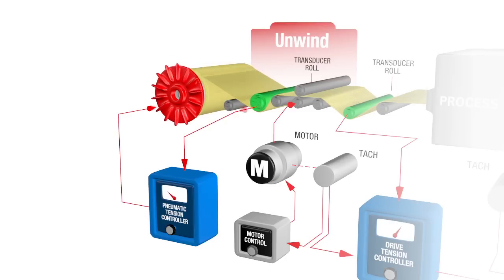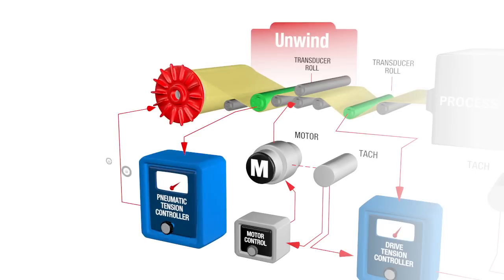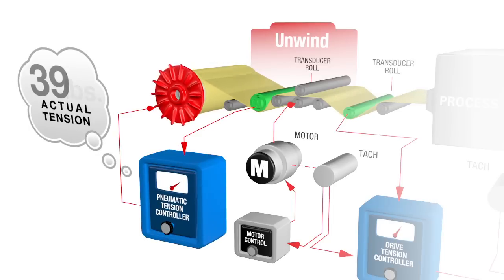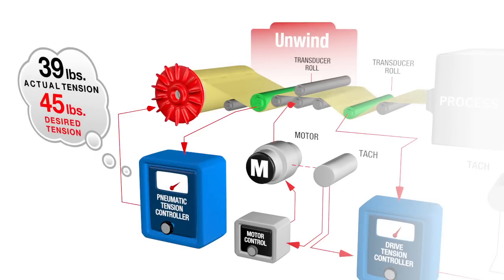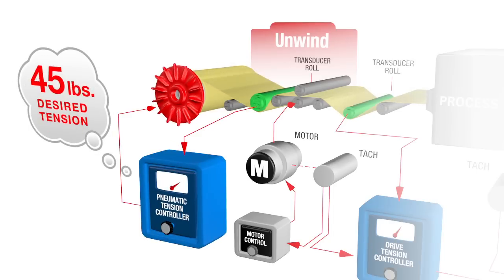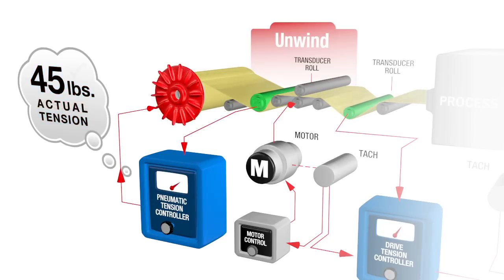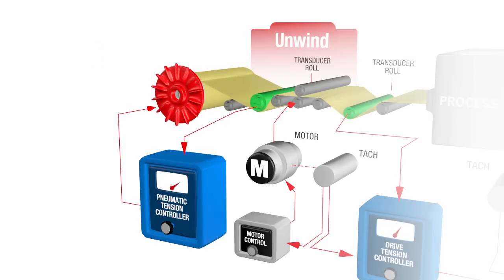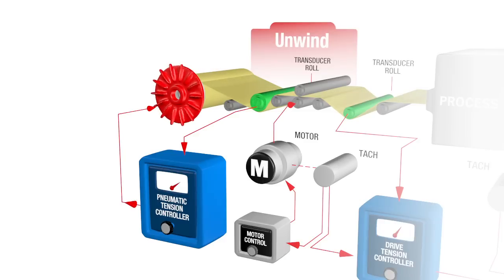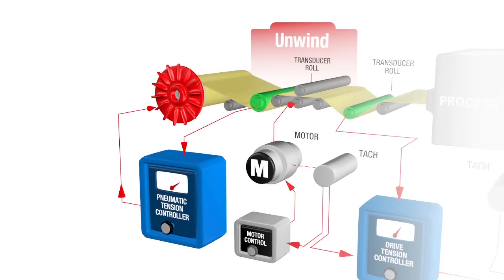During machine operation, the measurement signal from the tension transducers is input to an automatic tension controller. The controller compares the actual tension to a desired tension set point, input by the operator, and sends a compensated electric or pneumatic signal output to the control device. The output signal decreases as the material roll decreases in diameter to maintain constant tension going into the next tension zone.